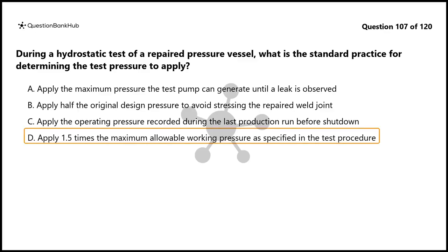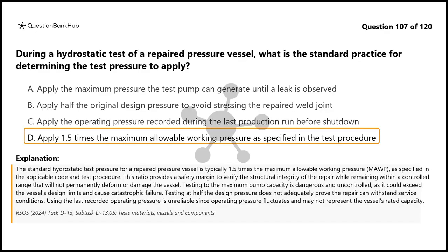The correct answer is D. The standard hydrostatic test pressure for a repaired pressure vessel is typically 1.5 times the maximum allowable working pressure, MAWP, as specified in the applicable code and test procedure. This ratio provides a safety margin to verify the structural integrity of the repair while remaining within a controlled range that will not permanently deform or damage the vessel.